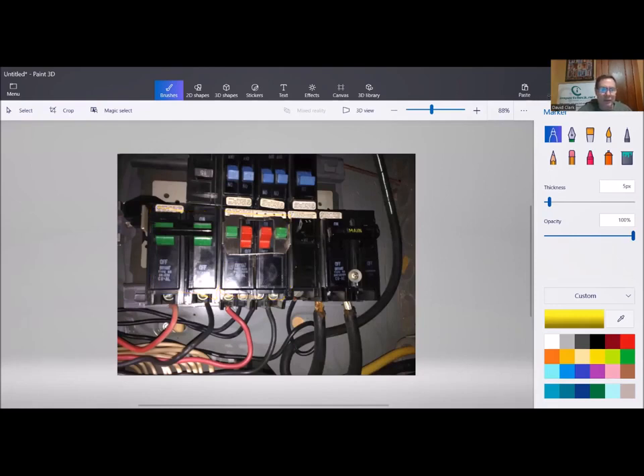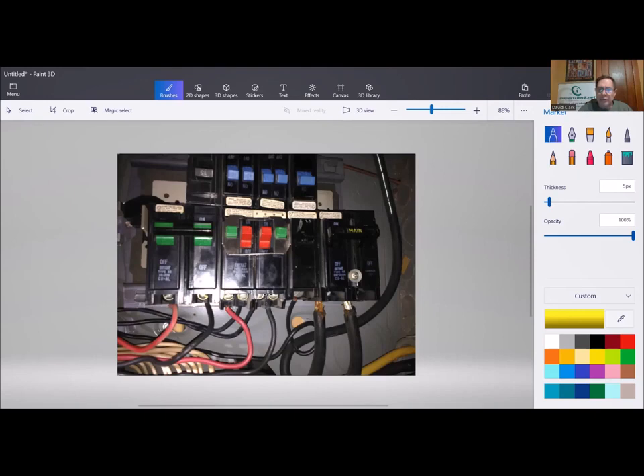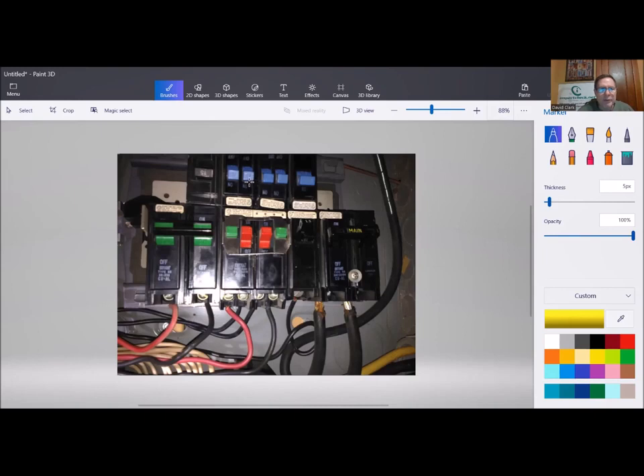So why would you use a quad breaker? Well, normally, you would use it if you need a 240 volt circuit, or maybe two 240 volt circuits. You can also use it for a multi-wire branch circuit. But there's some requirements for that. And we'll talk about that as we go along. If you look at the top, you'll see the minis, right mini tandem splits, whatever you want to call them, and they take the place of one breaker.